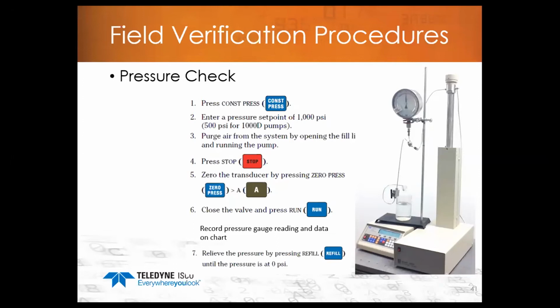Let me go back. I'm sorry. Before you do that, you'll want to adjust the potentiometer R61, your zero potentiometer on the pressure transducer board. You'll want to adjust that until you have a zero reading on the controller. So you'll adjust that potentiometer for a zero reading on the controller, then go ahead and press the zero pressure key on the front panel of the controller.